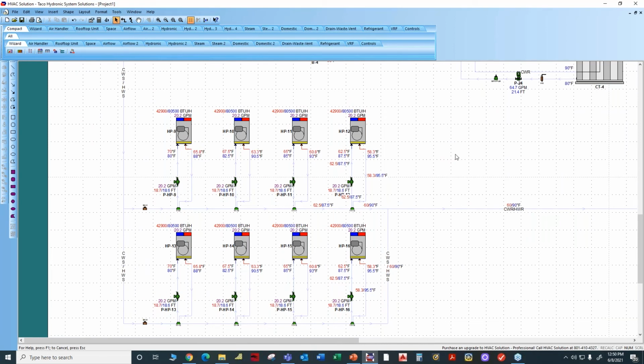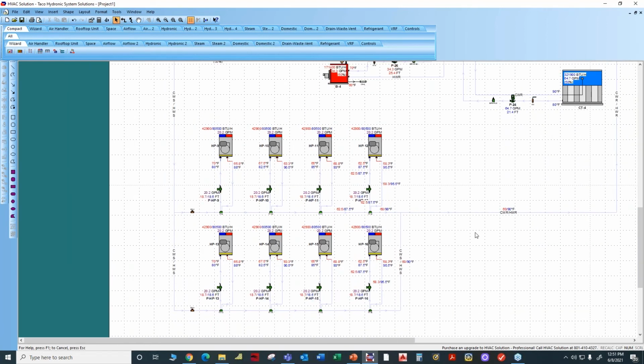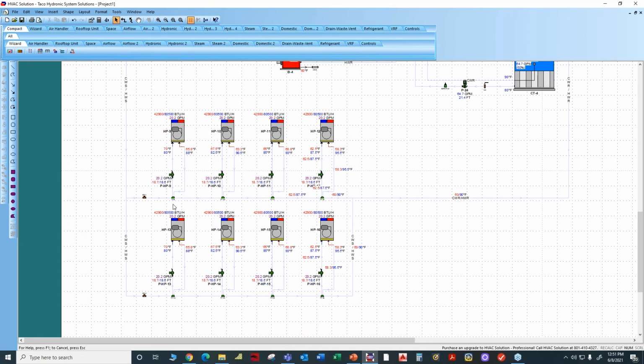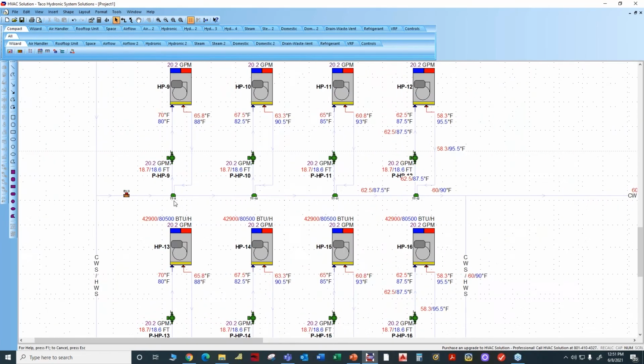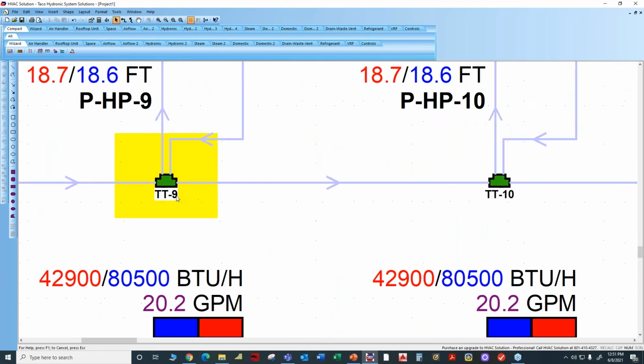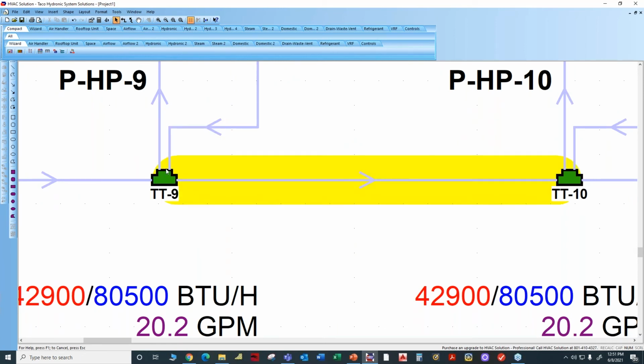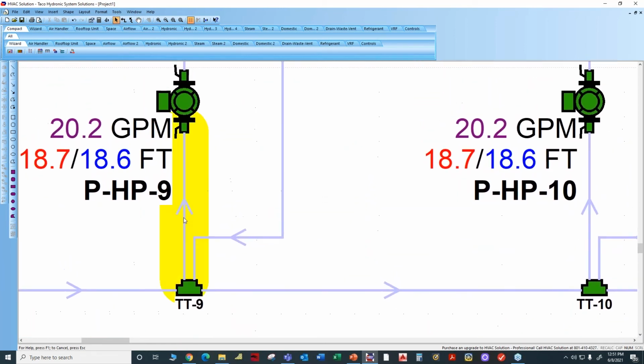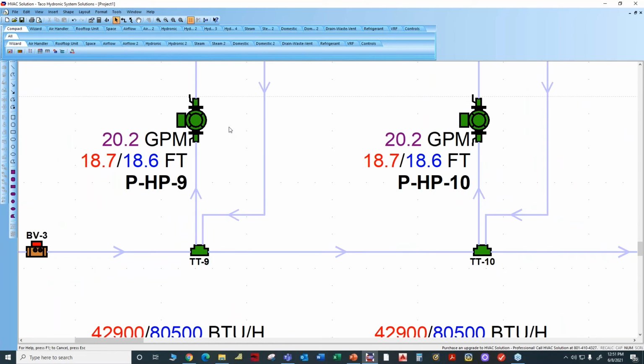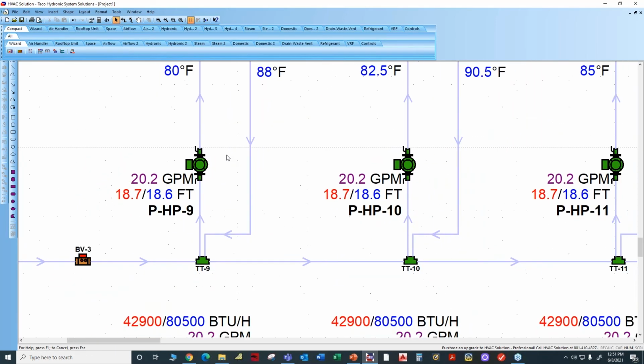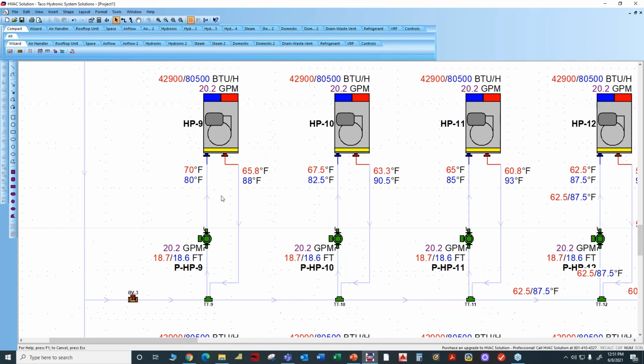Well, this is our load match system design, and the nice feature about this is, look at it, it's a single pipe from left to right here. There's only one horizontal pipe on each floor, and then we use a bridge, which we call a twin T. I'm going to zoom in to this little twin T. Hopefully you can see that. And we're using a circulator instead of a control valve. The reason we call it load match is because we're matching the GPM of the circulator, in this case 20.2 GPM, to each of the individual heat pumps.